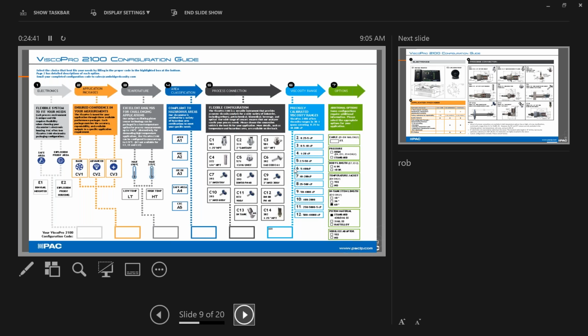What area classification do you need? What process sensor do you need? Your viscosity range, and then there's a number of different options like your cable length. Would you like your wireless adapter so you can communicate to the device with your cell phone? Is there any hydrogen sulfide in the fluid? That would require a Hastelloy piston. So there's a lot of different options here that you can specify. And what this ultimately does is give you a code that allows us to provide a quotation, allows you to place an order, and in the future will allow you to reorder the exact configuration.